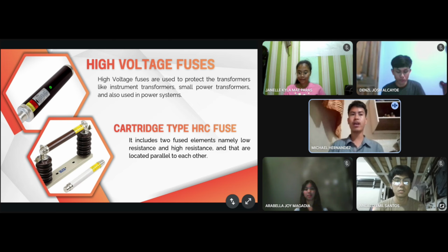When an overcurrent occurs, the metal element melts and vaporizes. But instead of causing sparks or flames, the powder inside absorbs the heat and safely stops the electrical arc. This allows the fuse to break the circuit very quickly and cleanly, even under high fault conditions. Because of this, HRC fuses are widely used in industrial plants, power systems, and high voltage applications where dependable protection is essential.